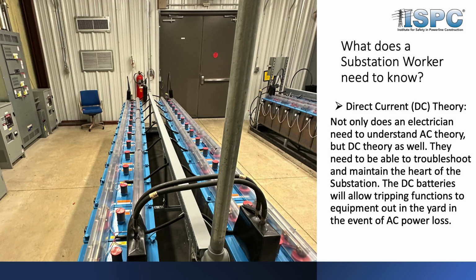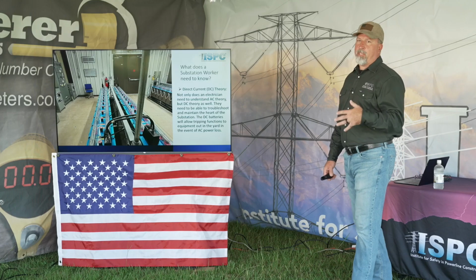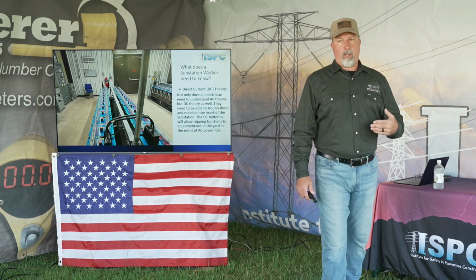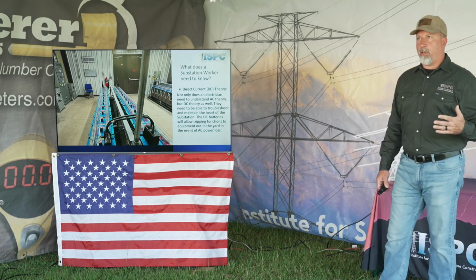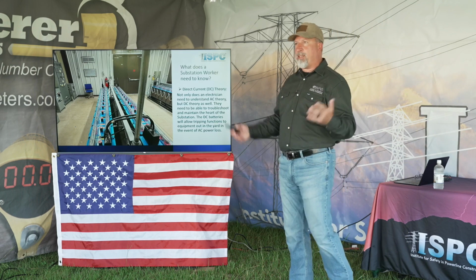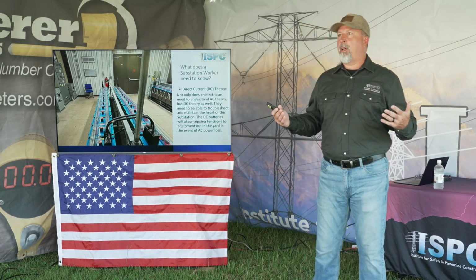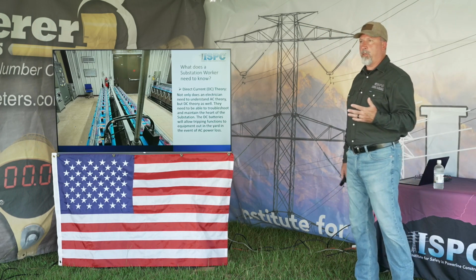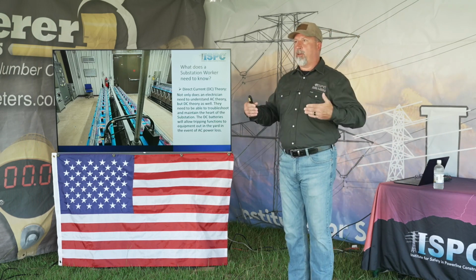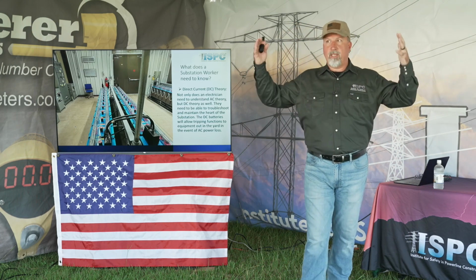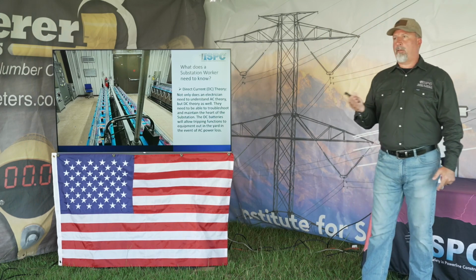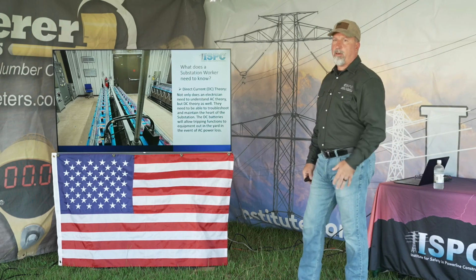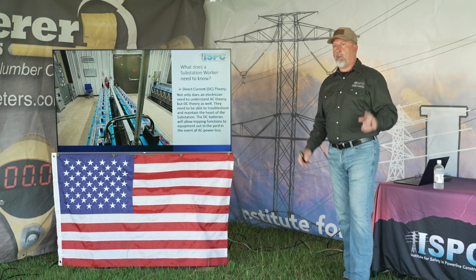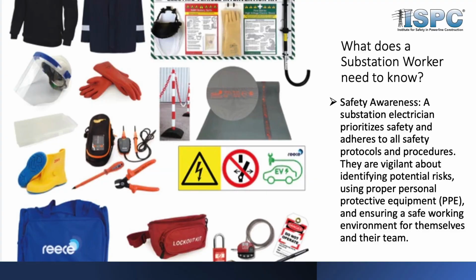It also provides a charge to the DC batteries so they're prepared should we have a power outage. That's when the DC battery comes into play, when we lose AC power to the station. These DC batteries allow operation of equipment, most normally tripping. So if AC power goes out, all your equipment's going to be in the status it was when the power went out. Obviously, when we bring that station back online, we don't want all that equipment already closed, because you'd essentially energize a line into that station and pick up the entire load. So the DC battery allows us to open those breakers up. This battery gives about a 16-hour window of support to the station without a charge, so we need to understand the DC side of things as well.